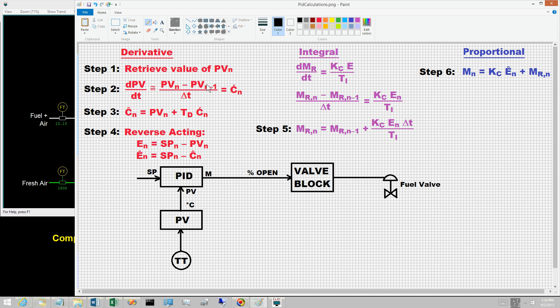The control calculations proceed as a sequence of steps, starting with derivative, then integral, and finally proportional. Step two computes the rate of change, C-hat sub n, for the PV. The simplest approach is a finite difference approximation: dPV/dt is the difference in PVs on successive sampling instances divided by delta t, designated as C-prime sub n. In practice, this simple approach is not satisfactory; a subsequent video will explain why and present a preferable approach.